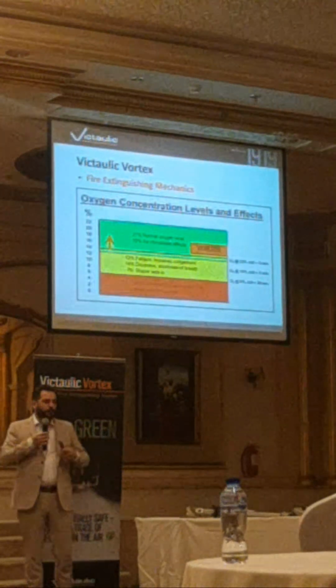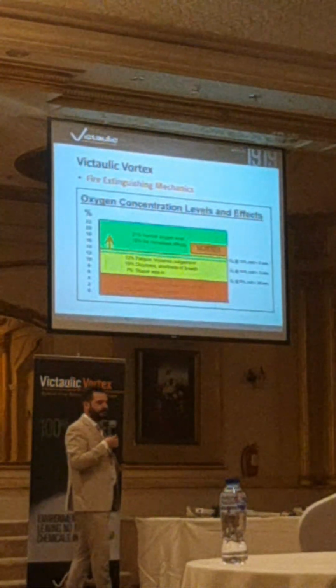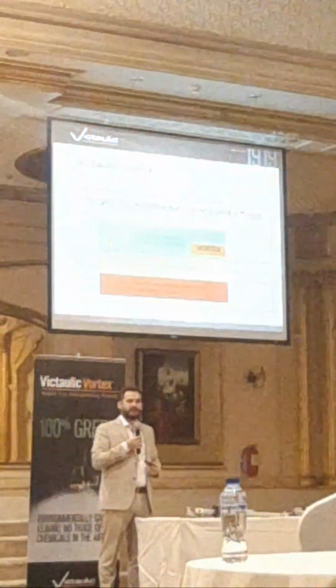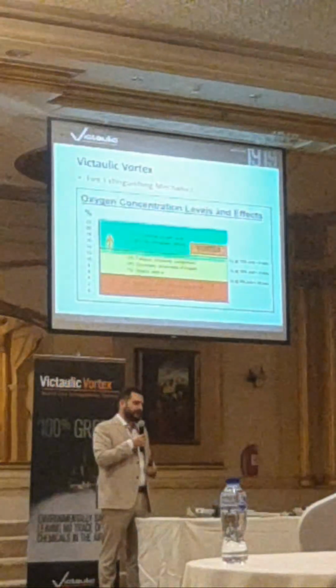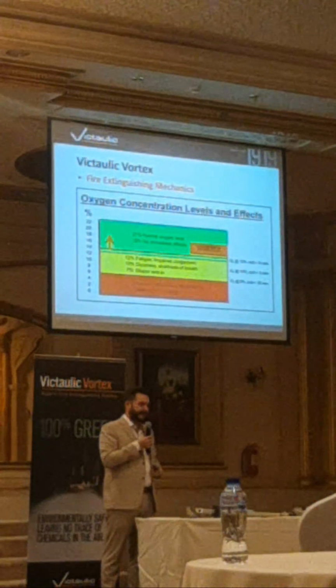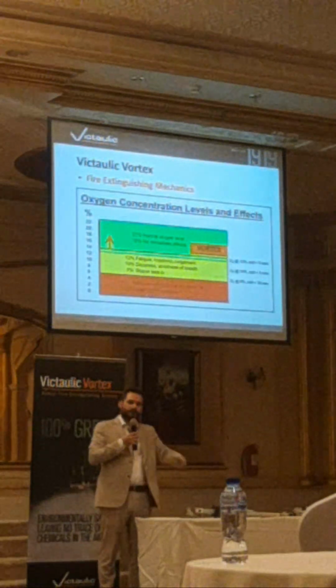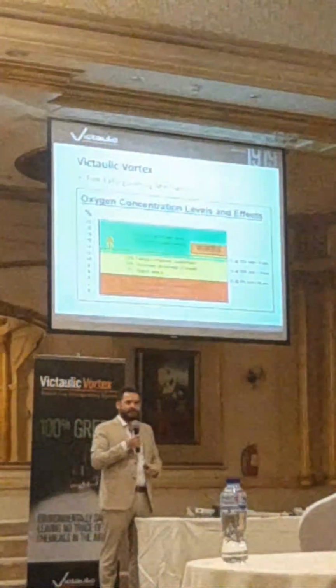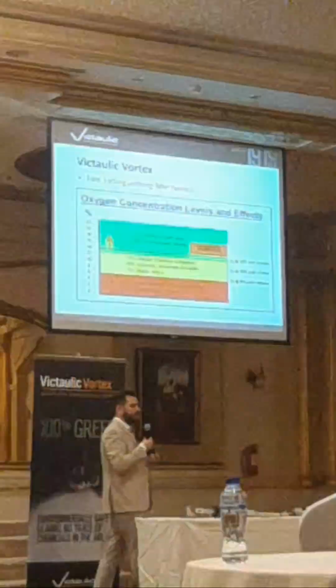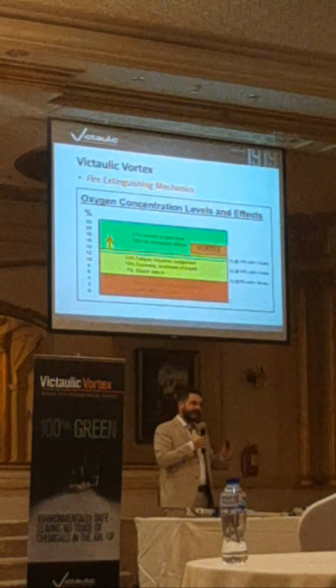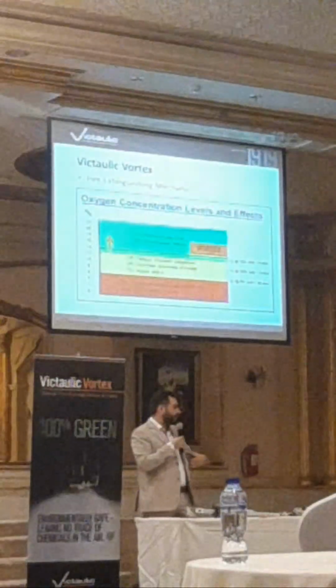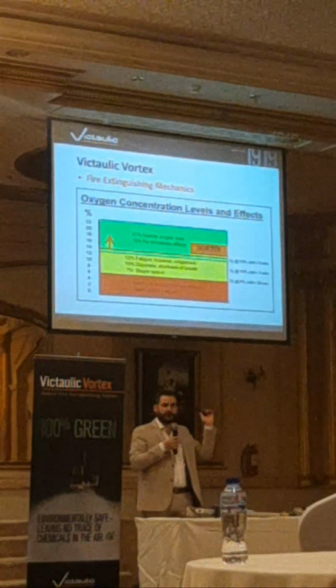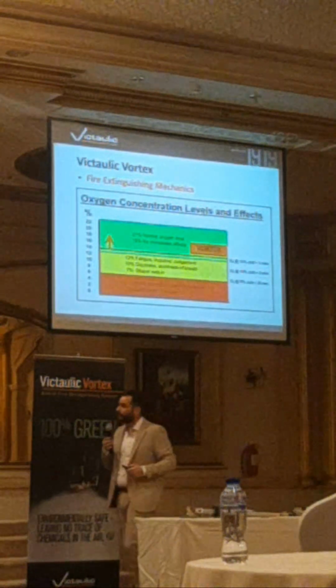system. When we're talking about life safety, the NFPA standard is stating that we're going to design between 12.5 and 16% of oxygen at the end of the discharge, meaning that you can have occupied spaces. This doesn't mean please stay in the room, play some cards with your colleagues before you leave. There's still a fire going on, and smoke of the fire can harm you more than the system itself. The point is that if you have a discharge and you are physically not capable of leaving the area, or the fire is between you and your exit, the system will not harm you. So that's according to the standard.